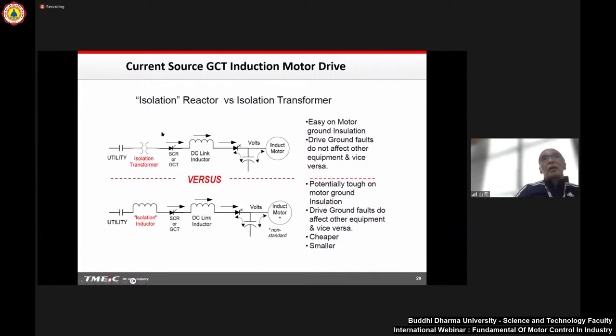And between the grounding and circuit, there is some capacitance, we call stray capacitors. Then as such voltage is applied, some leak current starts to flow into the ground. If this grounding circuit is not isolated like this one, this grounding current goes back to the utility side and may cause misdetection of grounding detection or something. So this is one of the differences.